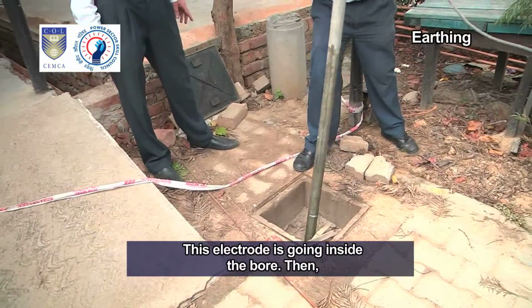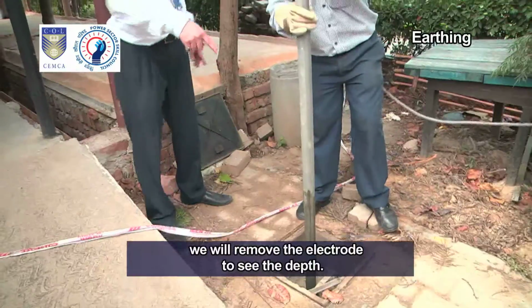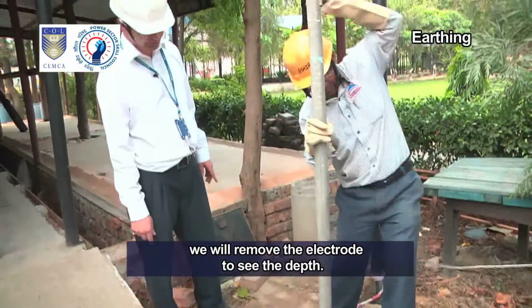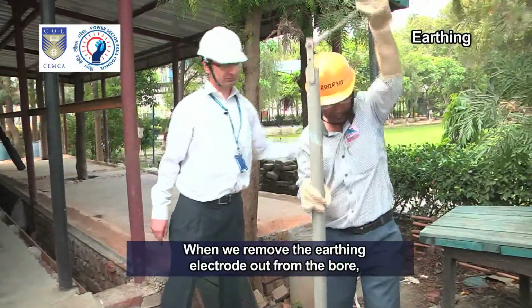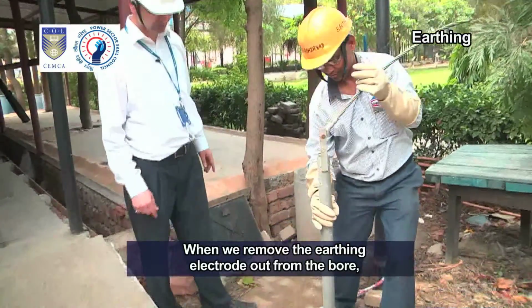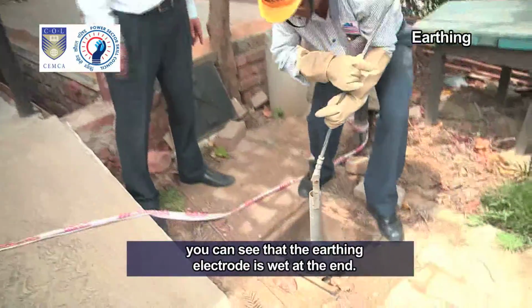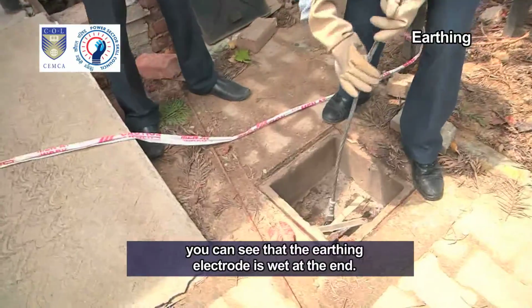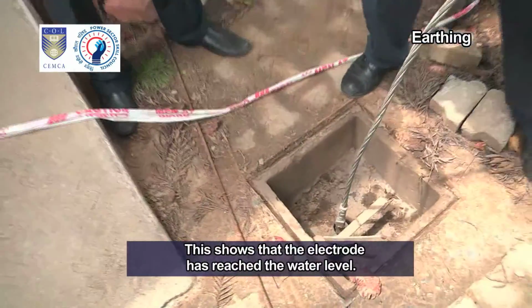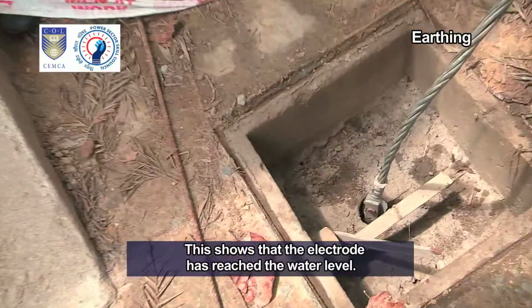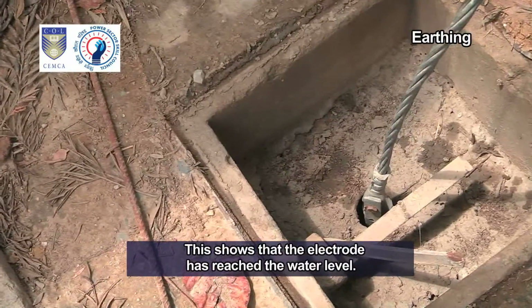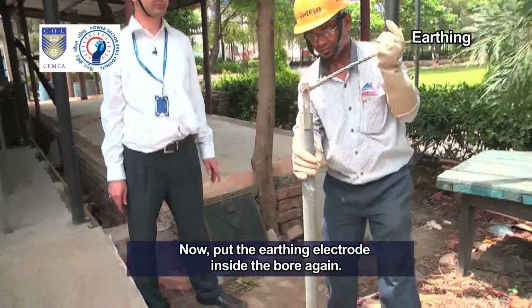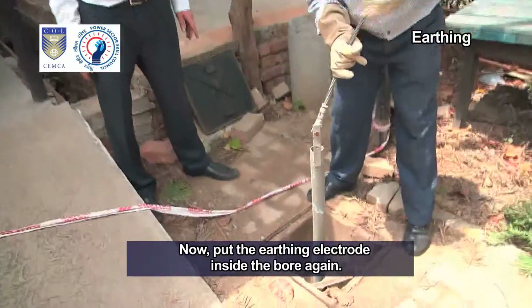This electrode is going inside the bore. Then we will remove the electrode to see the depth. When we remove the earthing electrode out from the bore, you can see that the earthing electrode is wet at the end. This shows that the electrode has reached the water level. Now put the earthing electrode inside the bore again.